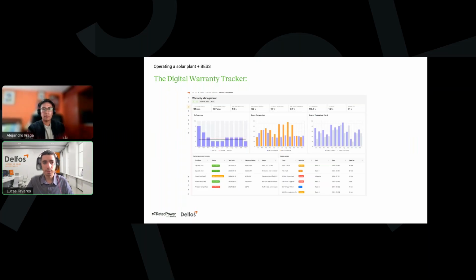Every time the BESS exceeds a defined threshold, whether a temperature spike in summer or abnormal humidity or excessive energy throughput, it's automatically logged, time-stamped, and contextualized with events and alarms. Over time, this creates a clear, auditable history that links operating conditions to performance tests, failures, and degradation indicators like delta SOH. Instead of debating months later whether a warranty condition was violated, you have objective, centralized evidence in real time. This is what makes a digital warranty tracker so powerful. It protects the asset owner, supports discussions with O&Ms, and turns data into accountability rather than just assumptions.